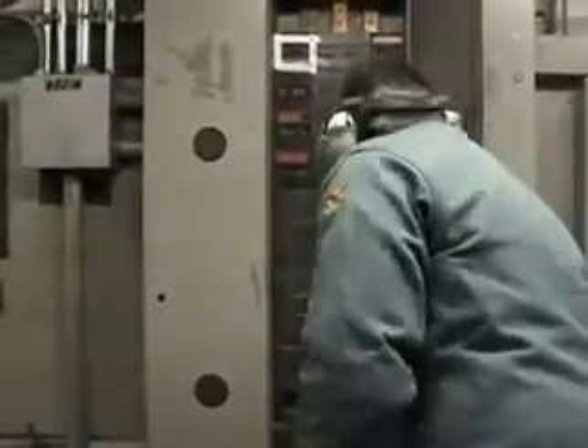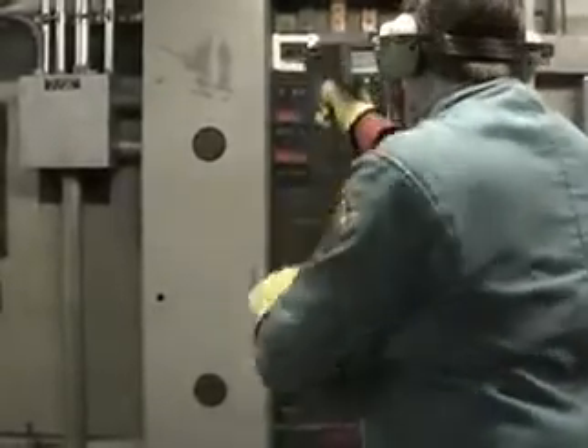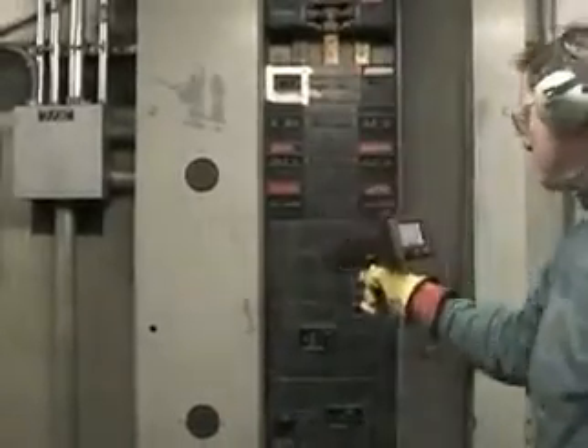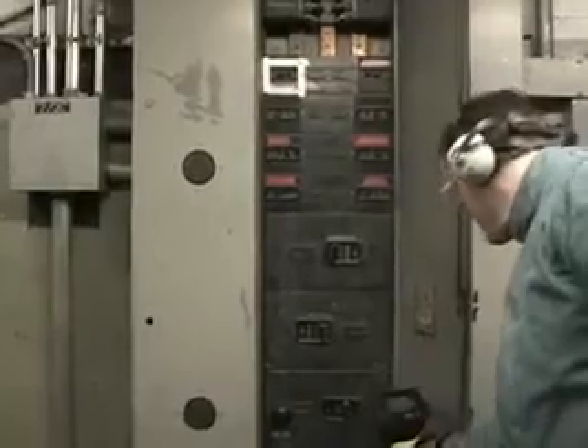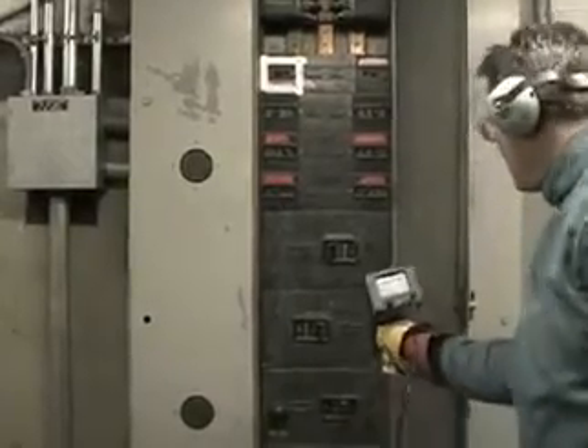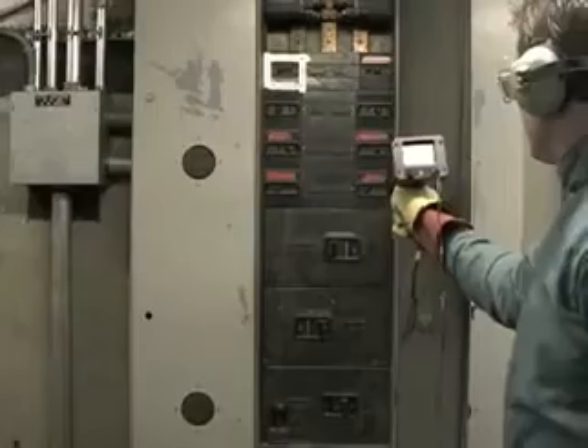We begin the service utilizing the ultrasonic probe. We're listening for noise generated by arcing, tracking, and corona. This provides a safety risk alert for the technician, as well as identifying hidden anomalies.